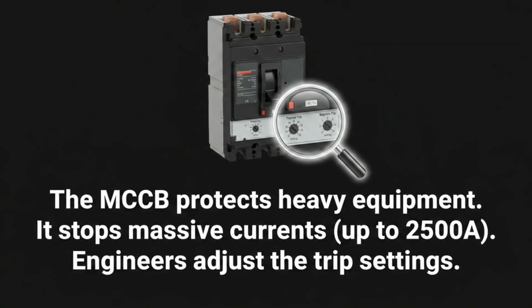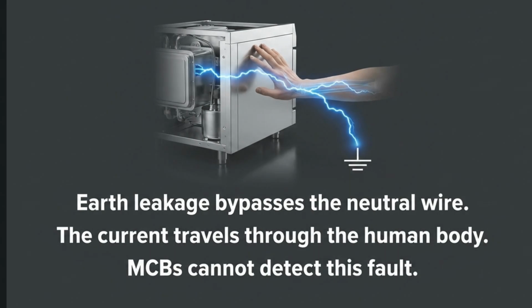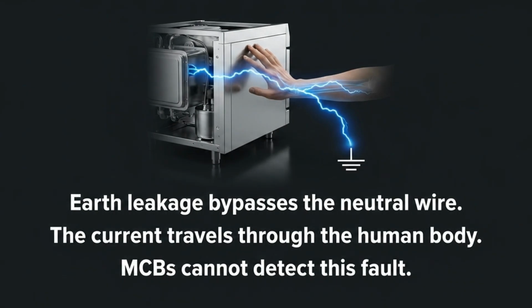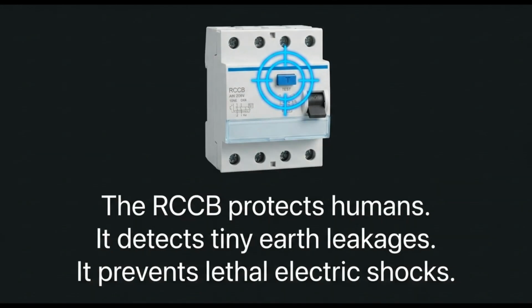For heavy industrial equipment, we use the MCCB, or molded case circuit breaker. It handles much higher currents, up to 2,500 amps, and often allows engineers to manually adjust trip settings. Standard MCBs cannot detect every type of fault. For example, if earth leakage occurs, the current might bypass the neutral wire and travel through a person, which the MCB won't recognize. This is where the RCCB, or residual current circuit breaker, comes in.